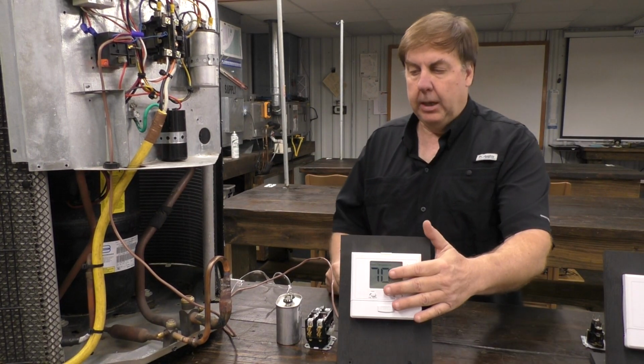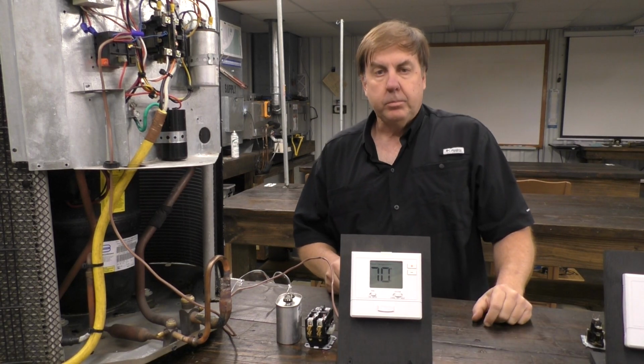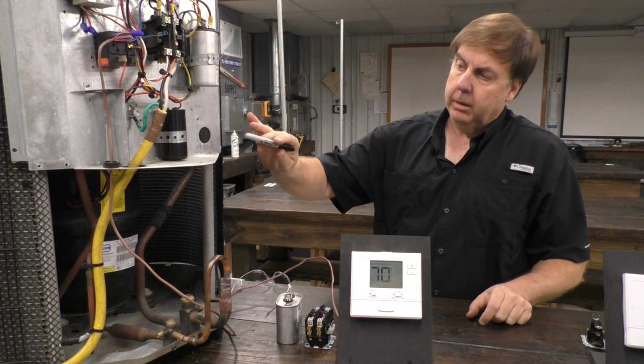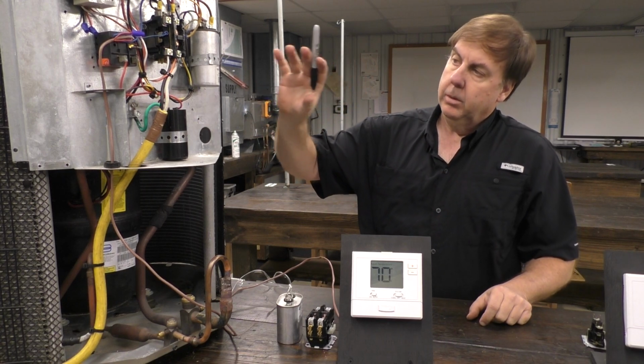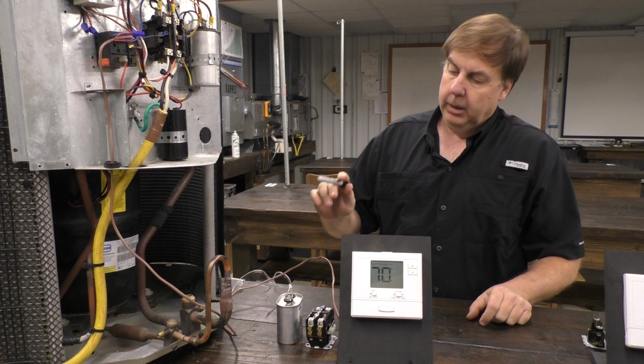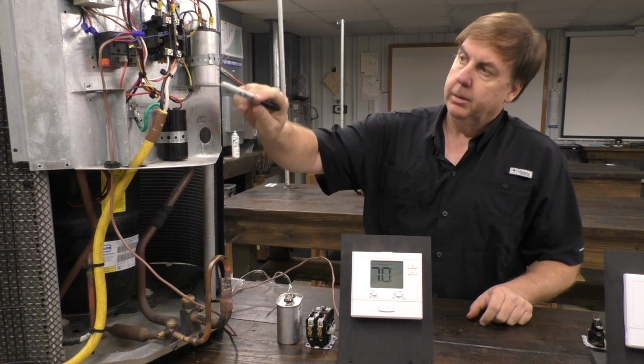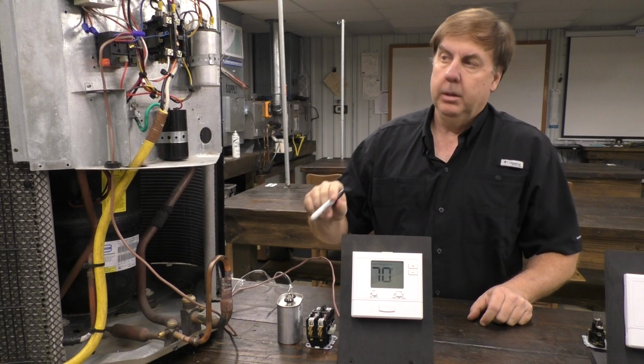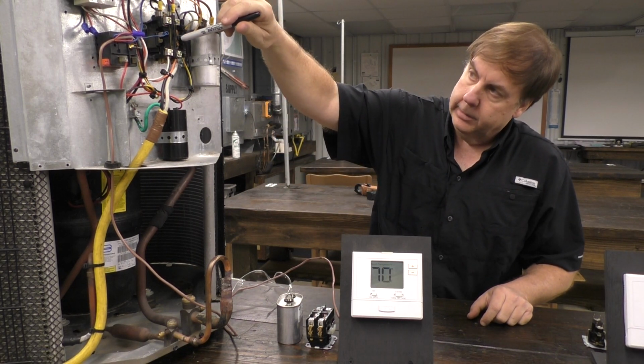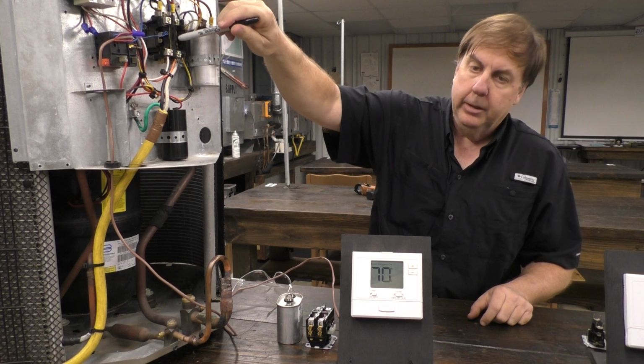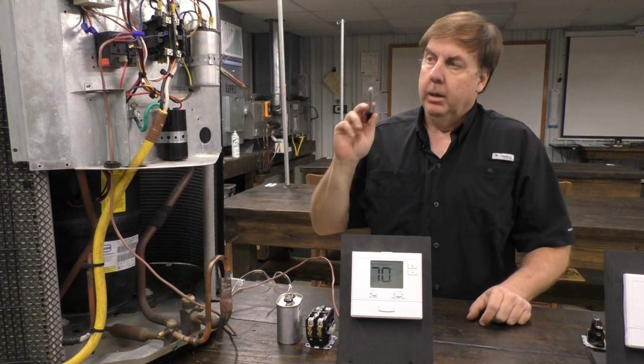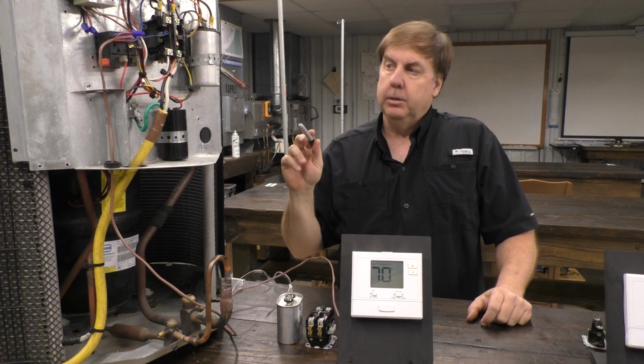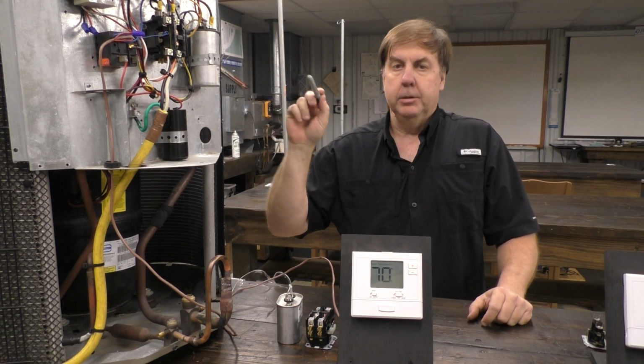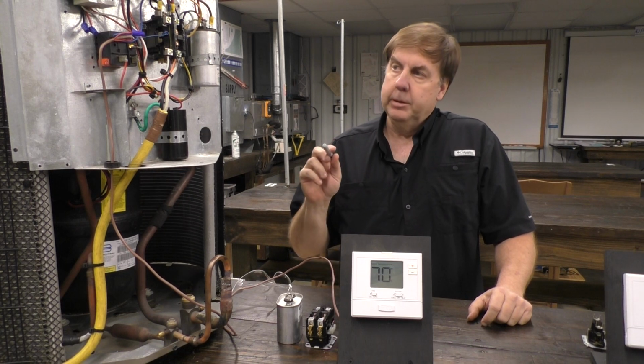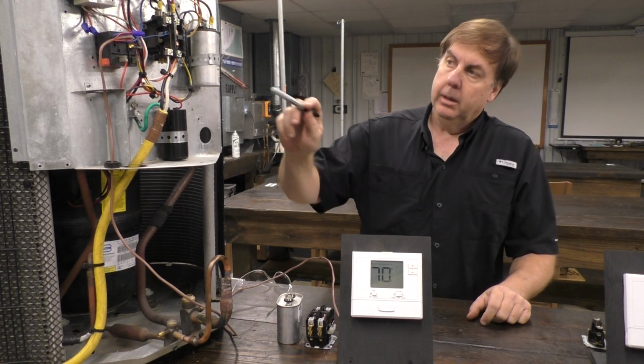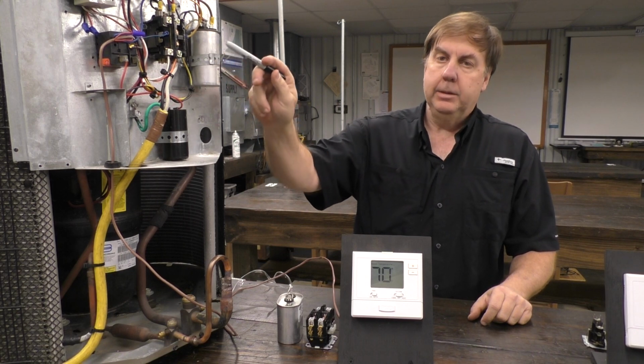Now say you turn the thermostat on and the unit still doesn't come on. We're outside at the unit, we've taken the cover off, and now we need to diagnose why it isn't running. I can start checking these components with my meter one at a time, which is time consuming, or I can start an elimination process. I come to the contactor and energize it. Immediately, with that one press, it tells me that most of these components are probably okay and that my problem is somewhere else. So now, logically, I'm looking at my contactor and wondering why isn't it pulling in.